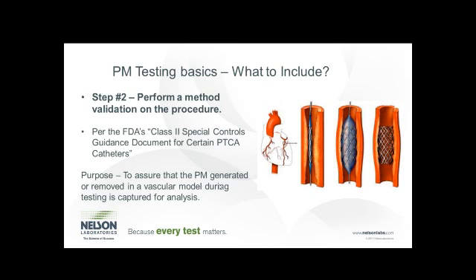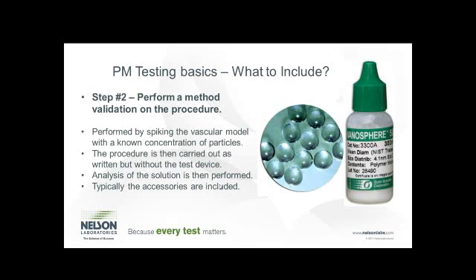The validation's purpose is not necessarily to show that particulate matter is removed from the device — that is a common misconception. In many cases, the device does not shed the full amount of the particulate matter that it may contain. The validation is to show that particulate matter exposed to that vascular model is flushed out and captured, so that it's included in the analysis. The important thing to remember is that the vascular model represents the patient, so if a great deal of particulate matter is generated but only a small part is actually flushed out or retained in the extract fluid analyzed, that is not an accurate representation of the particulate matter load exposed to the patient.